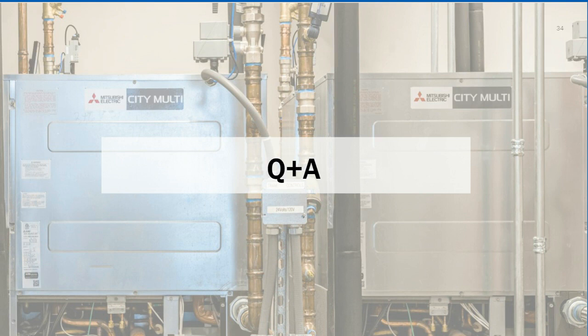All right, great. So was there any concern for freezing pipes in the water source system during the snowpocalypse? Yes, and we had some pipes freeze outside that were going to the cooling towers. After that happened, we replaced those, because they weren't insulated, and I believe they insulated some of those lines. It was a lot of the plastic stuff that was running underneath the cooling towers. So yeah, we definitely had some stuff freeze when it was 7 degrees.